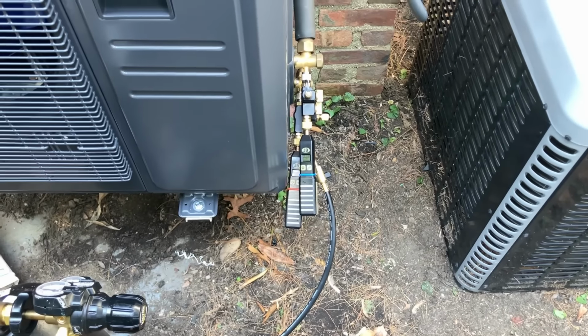Let's sit for 10 minutes, see what's going on. Now, since the previous system had a leak, we actually added 5 pounds of R410A beginning of last week, and according to the homeowner, about 3 or 4 pounds was added in April, and before that it never had to need any refrigerant. So because of the micro channel coil, we did see some issues with the indoor evaporator. We said, listen, when we fire up the system, we're going to make sure there's no leaks. So let's let this sit with that nitrogen, make sure we have no leaks, and hopefully we're good to go.